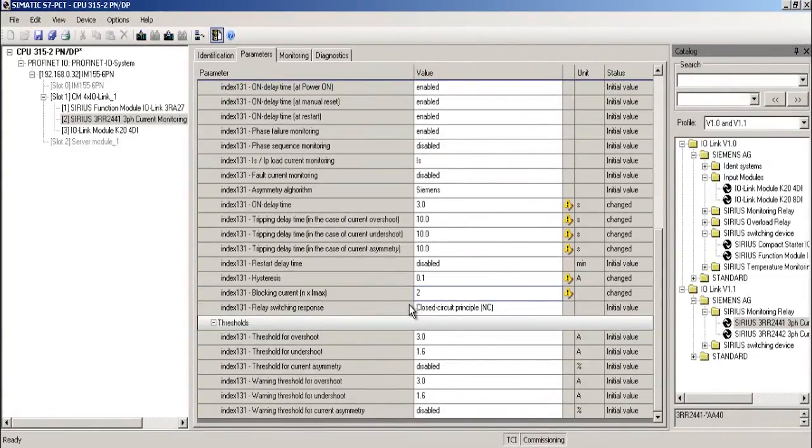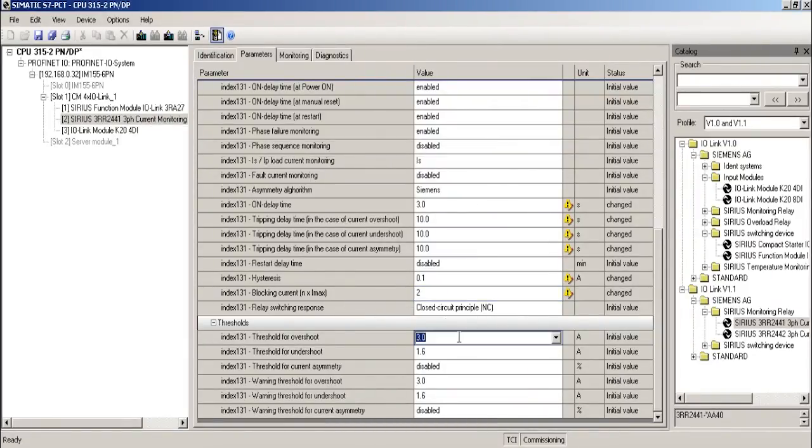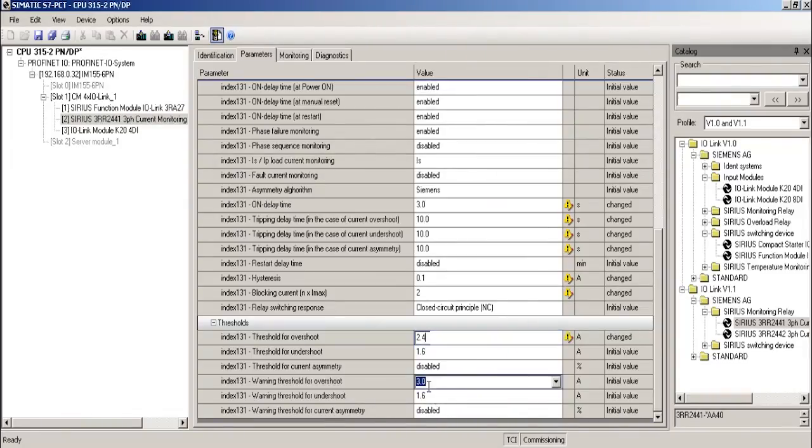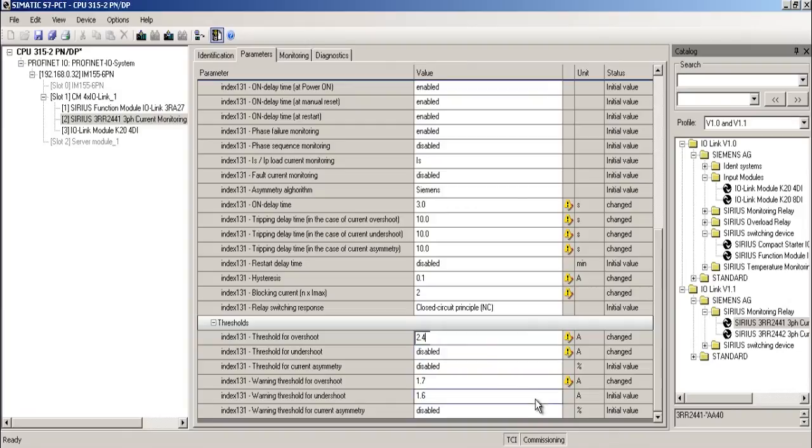Leave the remaining parameters as enabled or disabled or as closed circuit current principle. I define the threshold for overshoot as 2.4 amperes. I select 1.7 amperes for the warning threshold for overshoot. The remaining values are disabled.